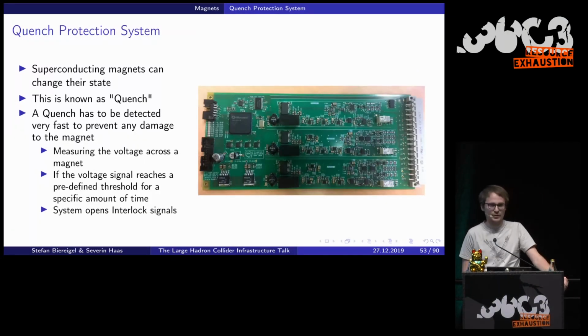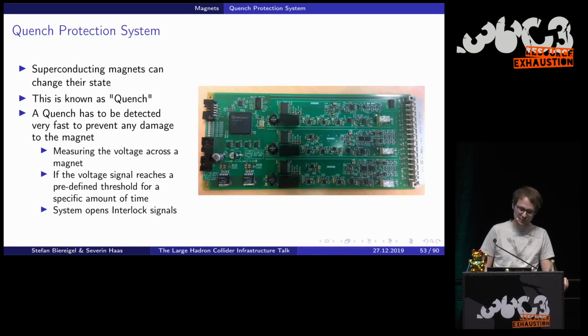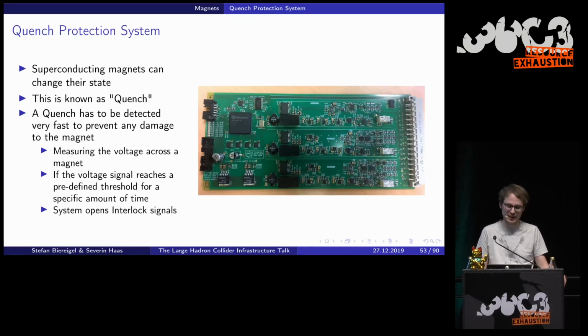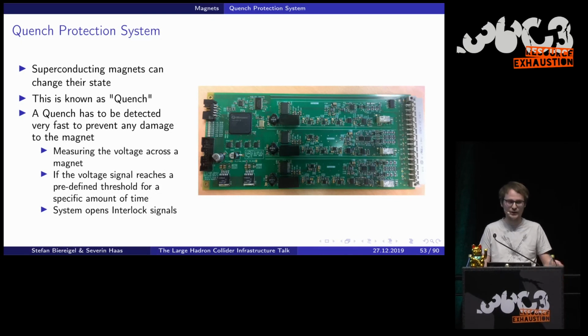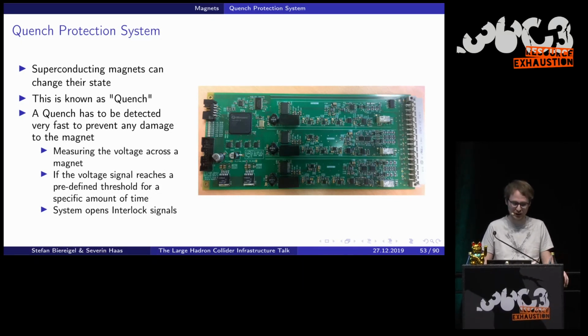Superconducting magnets have some benefits, but also some downsides. Sometimes they change their state because there are small vibrations in the magnet, or the temperature is not precise enough, or the current is too high. Then they change that state, and it's called a quench. We can detect a quench when we measure the voltage across the magnet, because the resistance changes at this point. When there's a quench, the resistance changes quite rapidly, in milliseconds, and we can detect this voltage rise with sophisticated electronics.